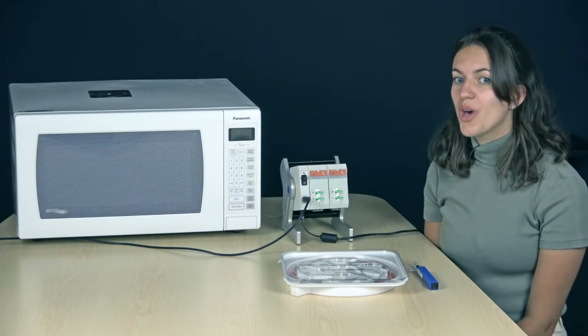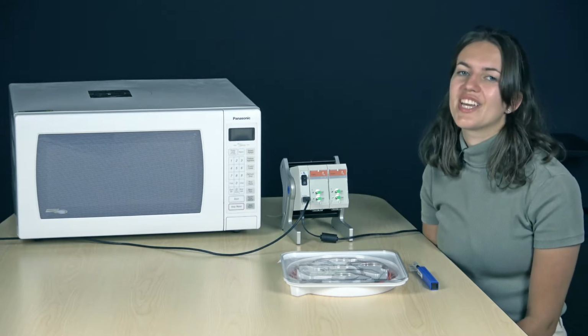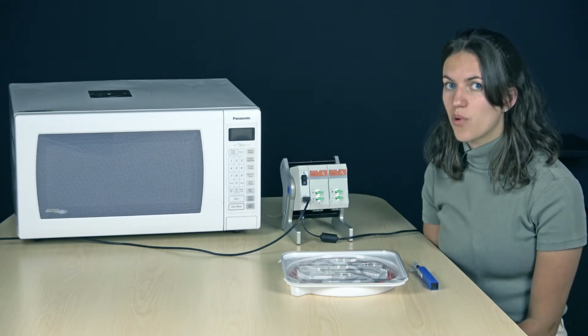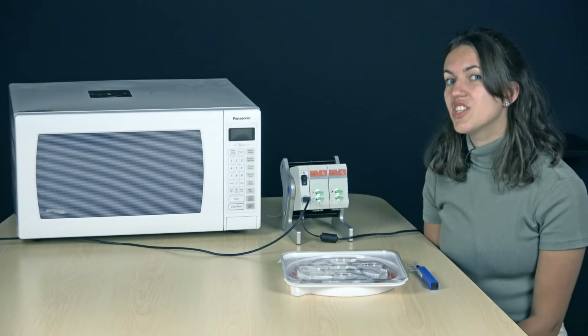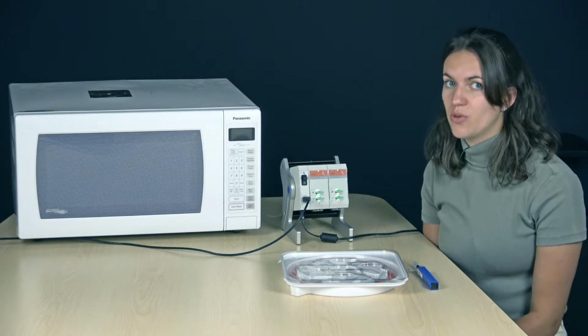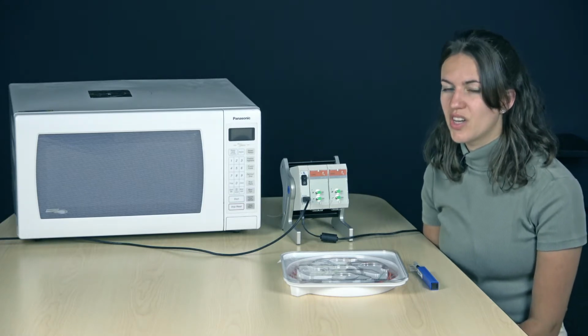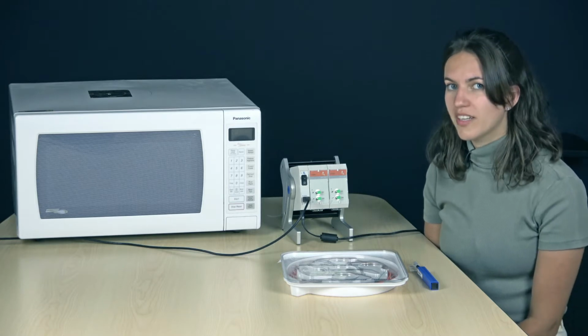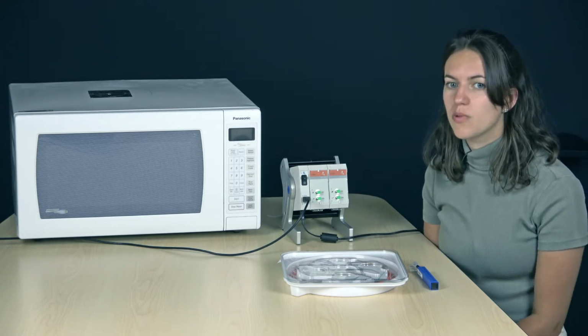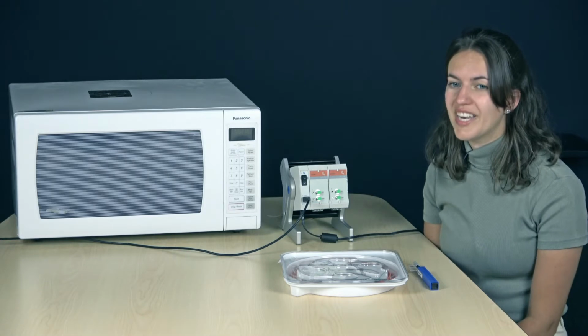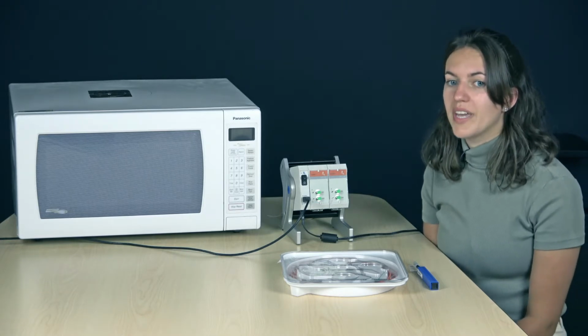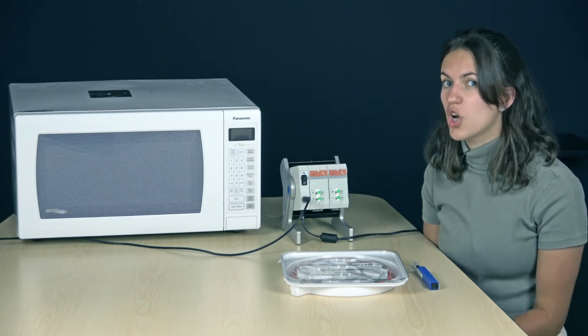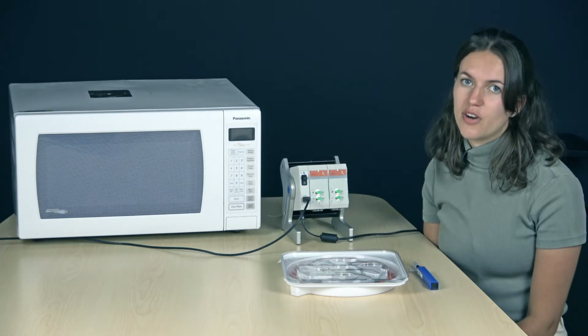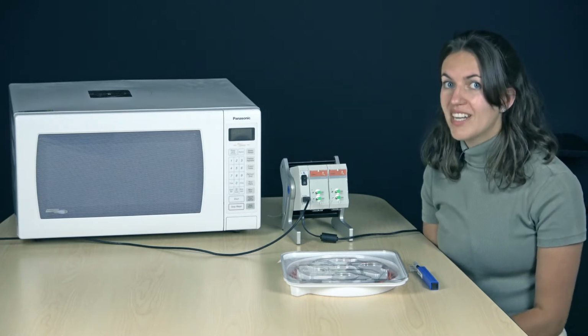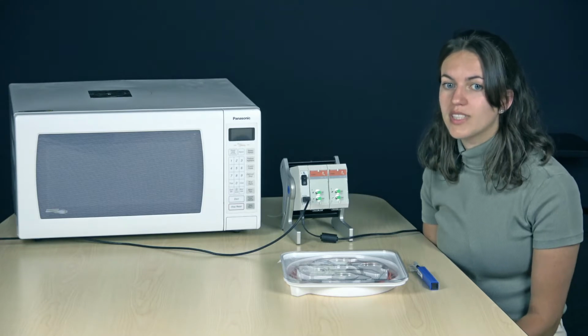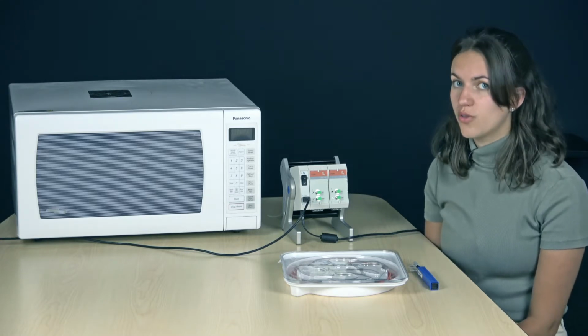In this video, 3 types of tissues will be heated in a microwave to simulate the heating process of an ablation probe. The temperature will be monitored by Physio's temperature fiber optic sensors. Ablation probes usually generate constant power of radio frequency waves which lead to non-uniform heating of tissues. This effect will be enhanced if different types of tissues are targeted by the ablation because of their difference of conductivity. Penetration variation of radio frequency wave also contributes to non-uniform heating.